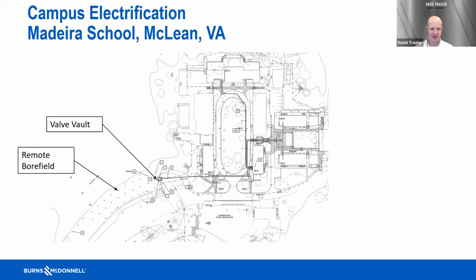This is a snap from one of the design documents showing, on the left, the remote bore field, the valve vault, and the piping running underground from the vault to one of the dormitory buildings, where it was manifolded together and pumped throughout the district. That water would return and go back out to the bore fields. Each building also had energy recovery within it, so it would recover energy in the building first before drawing additional energy from the bore field.